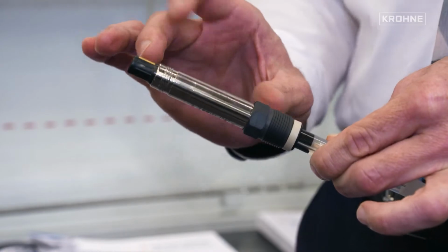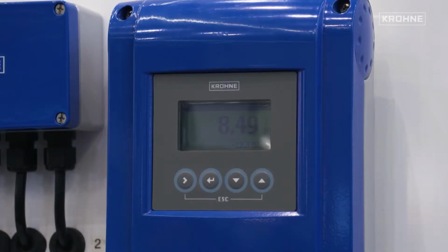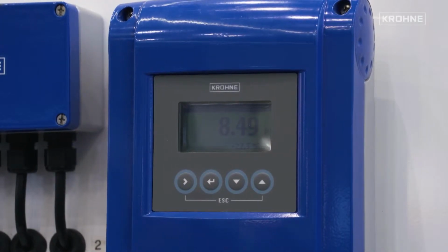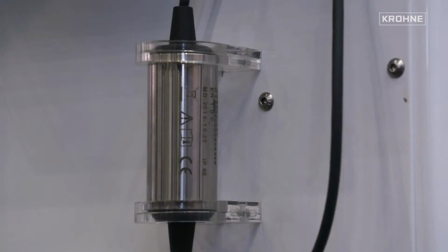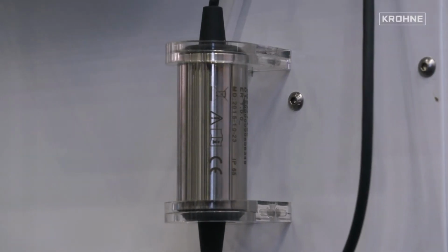So what we offer this customer is a HART communicator built into a housing like a standard transmitter, and with this HART communicator he has complete access to the sensor. He can read out all the values, do a calibration, look into the logbooks, whatever is needed.